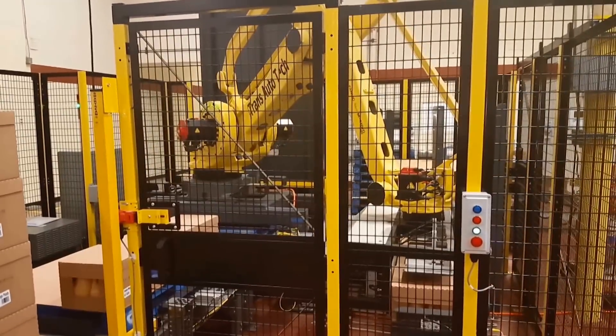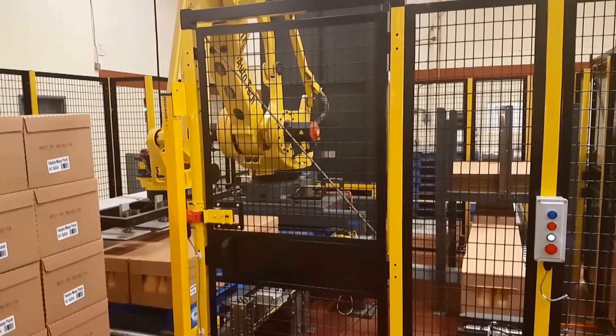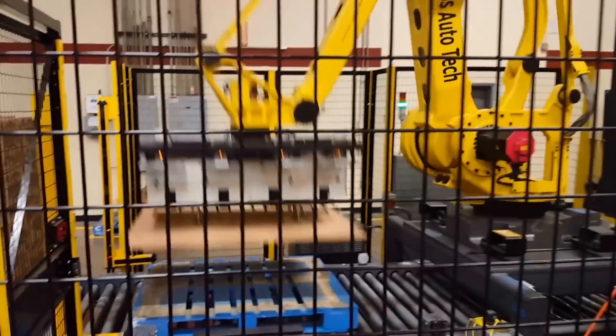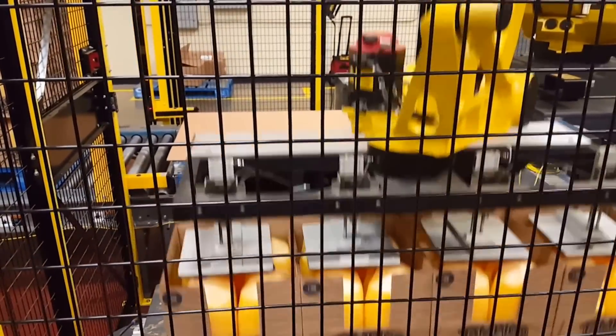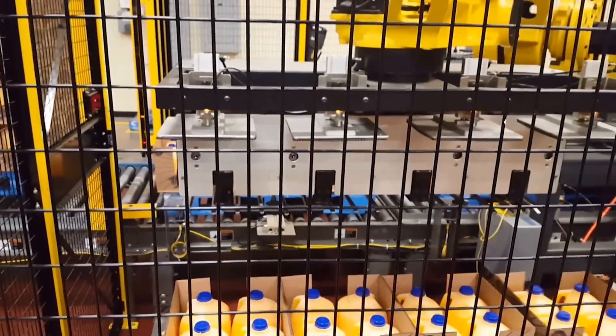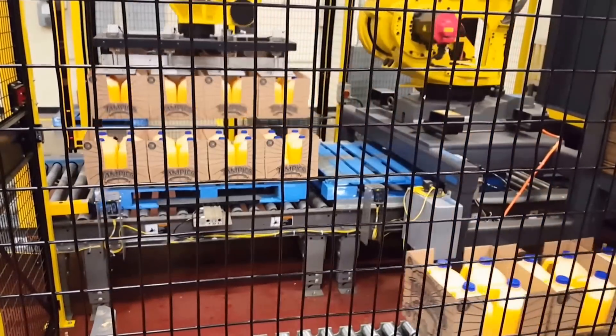While building a pallet stack, the FANUC M410IC 185 robot picks full cases from the powered roller infeed conveyor, four cases per pick. This equates to a product payload of 156 pounds on each robot cycle. The robot end-of-arm tool, designed and built by Trans Automation Technologies, has steel tines that mesh between the conveyor rollers, allowing the robot to pick by lifting cases from the bottom and clamping the top of the case for stability and travel.